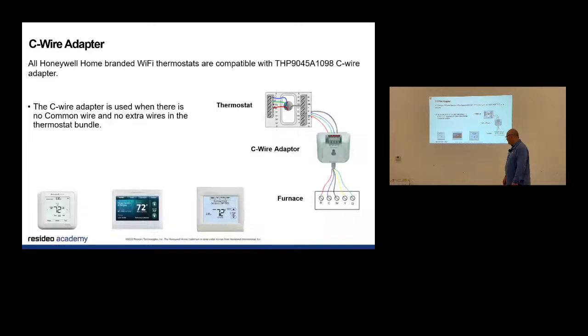Oh, here's something. A while back we were talking about how old homes often have 4 wires, right? I need a common, so I need a 5th wire for Wi-Fi. You guys have these on the shelf, I guarantee it. And by the way, it works for other brands. This is your 4 wires coming from an existing thermostat. You put this down in the furnace cabinet, take the existing wire off the furnace board, wire it in here, and match the thermostat wires: a C, an R, a W, and a G.